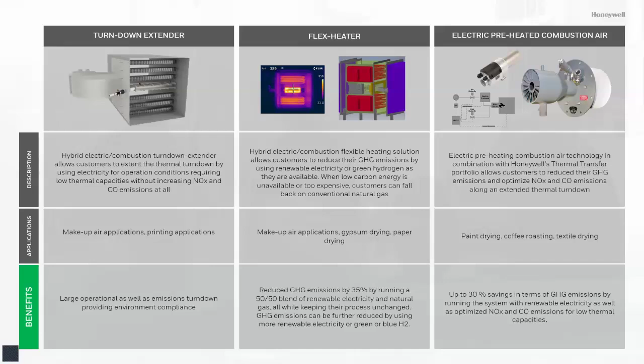Here we use the electric flow heater to optimize the combustion by providing the burner with preheated combustion air, depending on different demand signals as well as temperature points throughout the process. So we're augmenting the burner with a small electric heater to make the burner better.